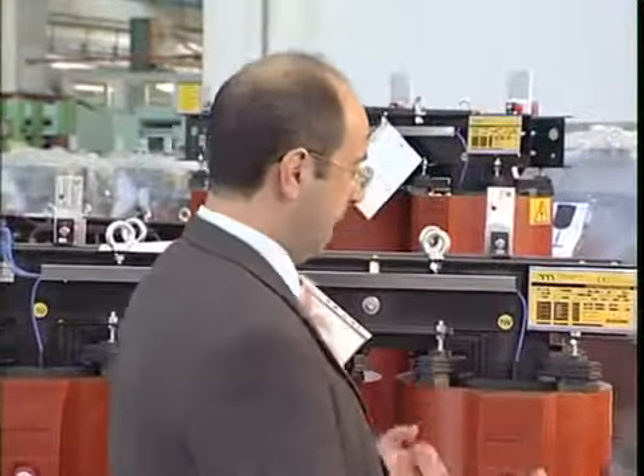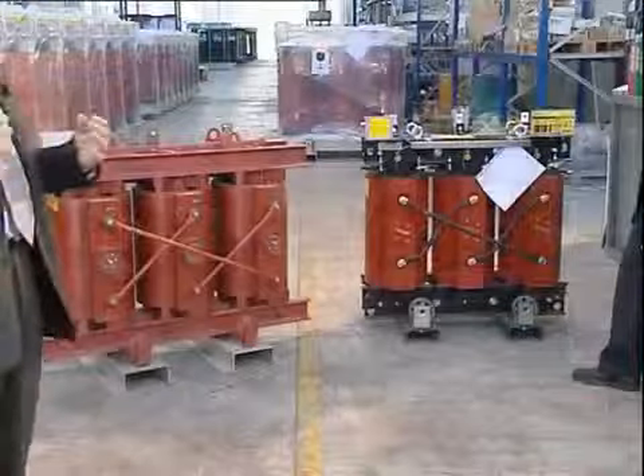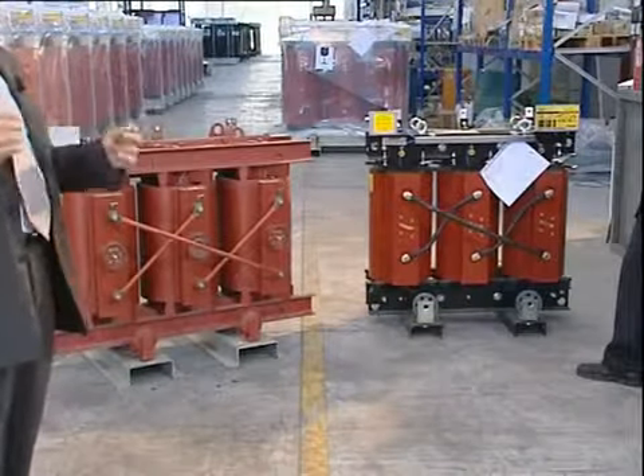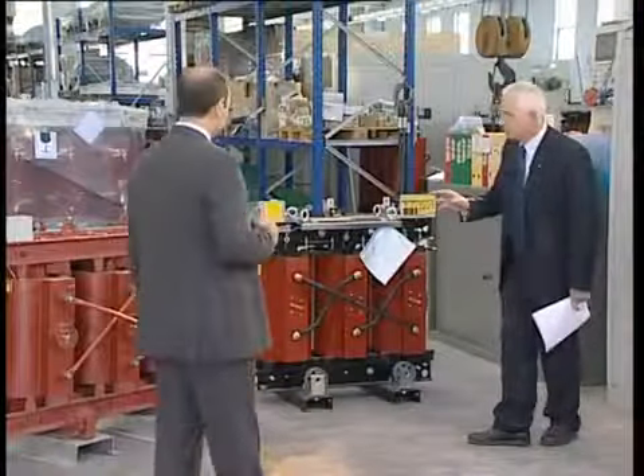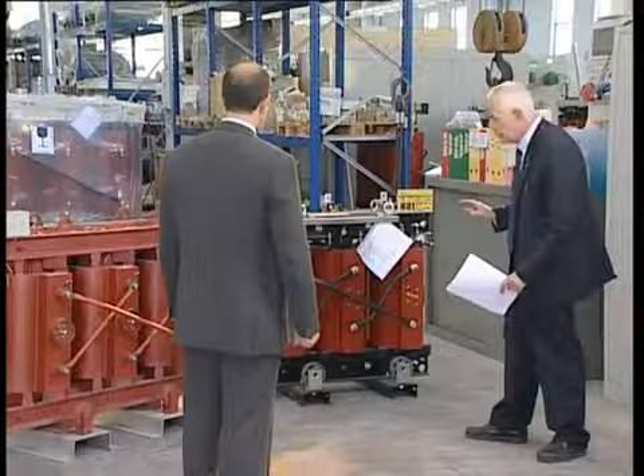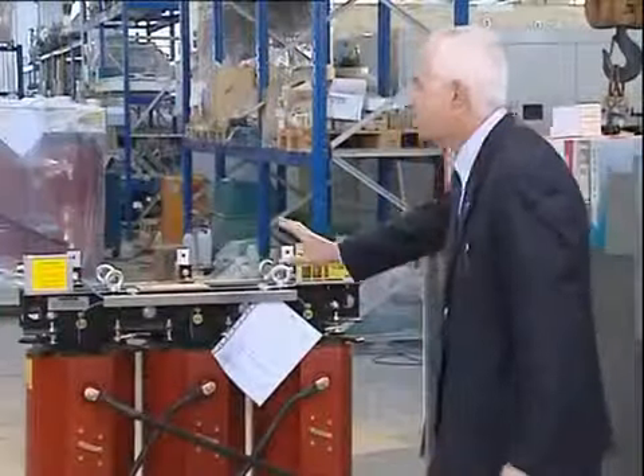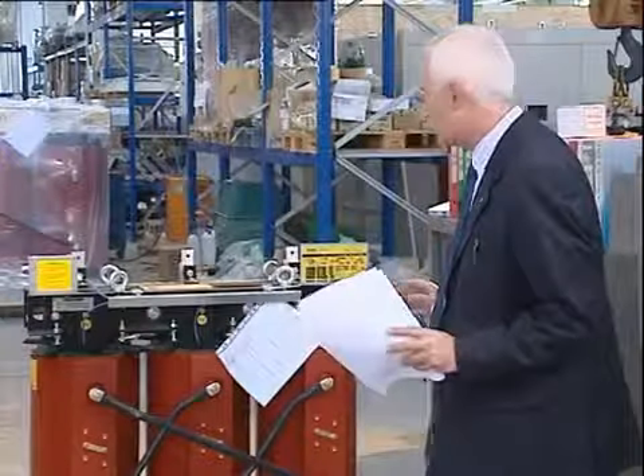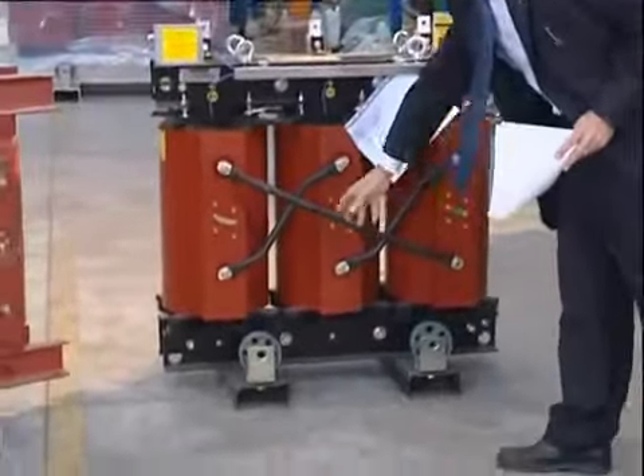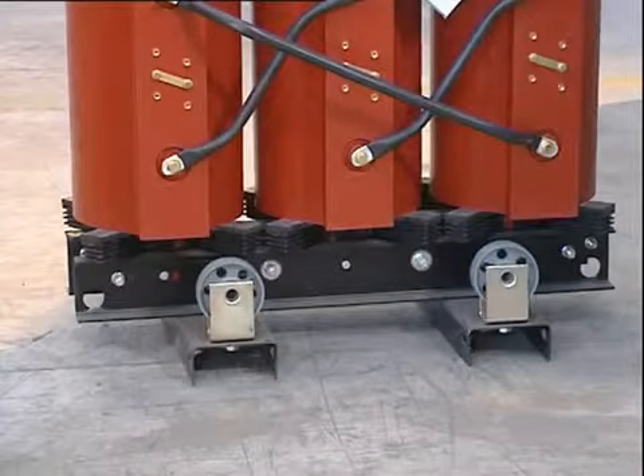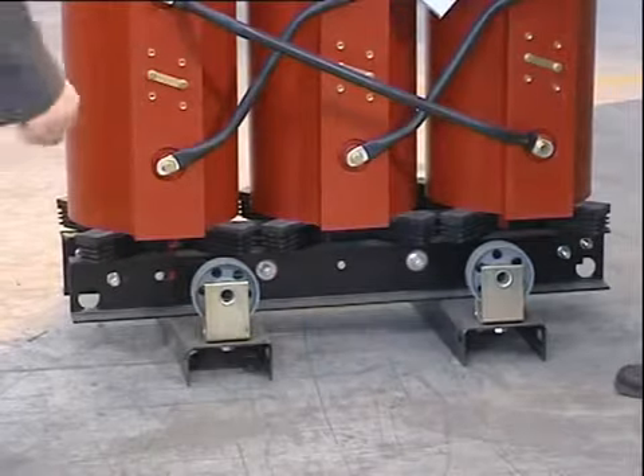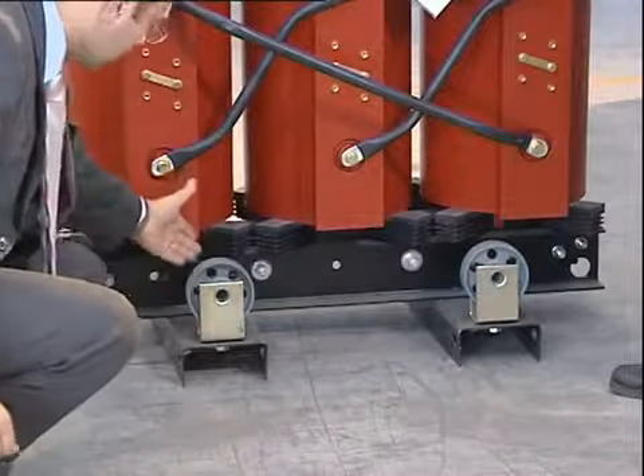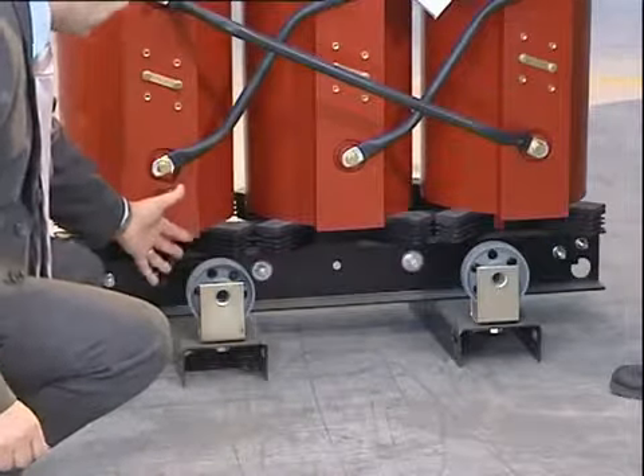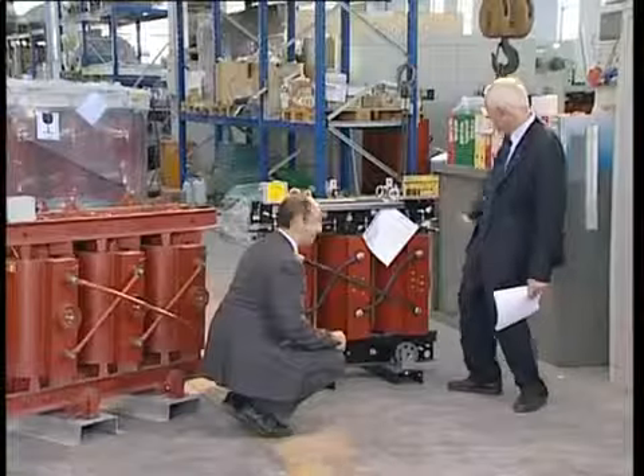At first sight, the transformer produced by our competitor may look fairly sturdy and therefore better than ours from a qualitative viewpoint. However, if we took a closer look, we would notice that that is not really the case. Looking at these two transformers, regardless of the fact that I might be biased, I would say first of all that, on the contrary, this one looks much more balanced in terms of size, starting from the wheels and the supporting structure. Indeed, we can see that our transformer is fitted with U-shaped beam structure and with cast iron 125mm wheels, perfectly compatible with the transformer's weight, which is 700 kilograms.